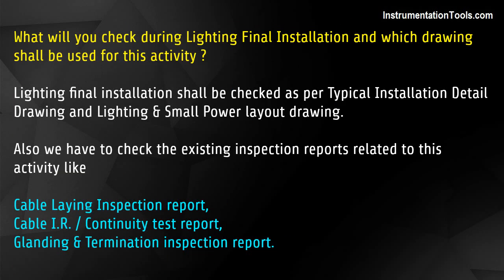What will you check during lighting final installation and which drawing shall be used for this activity? Lighting final installation shall be checked as per typical installation detail drawing and lighting and small power layout drawing. We also have to check existing inspection reports related to this activity, like cable laying inspection report, cable IR continuity test report, and glanding and termination inspection report.